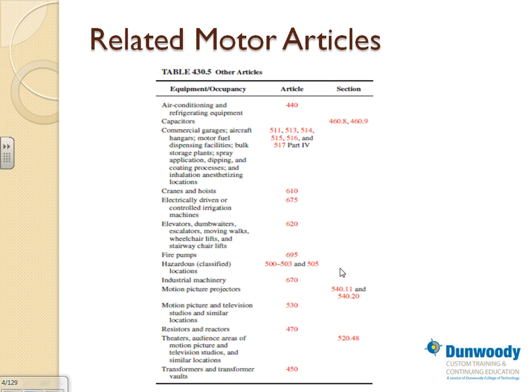When we talk about motors, guys, there are so many special motors. For example, with AC equipment, if you couple a motor with a compressor, the whole combination acts differently. So the code makers decided to group them in a standalone Article 440, instead of putting them in 430: a fan motor, a blower motor, anything that has a compressor, refrigeration equipment, chillers and so forth. When you have a compressor coupled with it, the motor will act differently.